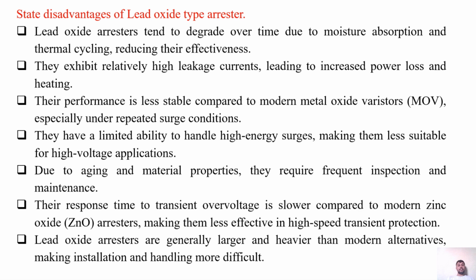State the disadvantages of lead oxide type arrestor. So there are several disadvantages of this type of arrestor. Some are listed over here. Lead oxide arrestors tend to degrade over time due to moisture absorption and thermal cycling, reducing their effectiveness. They exhibit relatively high leakage currents, leading to increased power loss and heating. Their performance is less stable compared to modern metal oxide varistors (MOV), especially under repeated surge conditions.